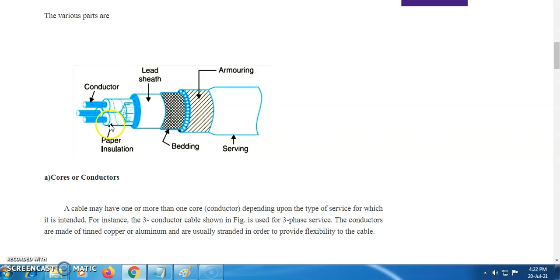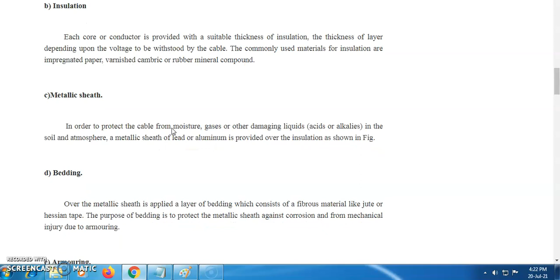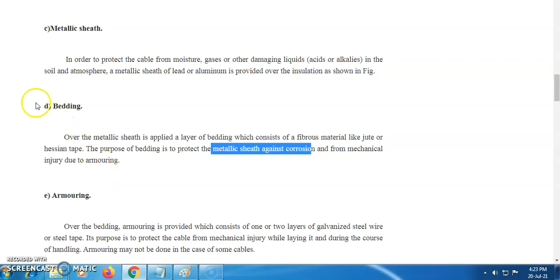The third layer: the first layer is insulation, second is sheath, and third is bedding. Bedding is nothing but a layer applied over the metallic sheath which consists of a fibrous material like jute or hessian tape. The purpose of bedding is to protect the metallic sheath against corrosion. It is provided so the metallic sheath does not oxidize, and the jute layer acts against corrosion and mechanical injury. A big mechanical injury should not come directly to the metal sheath. That is why bedding is provided. And the next layer is armoring.